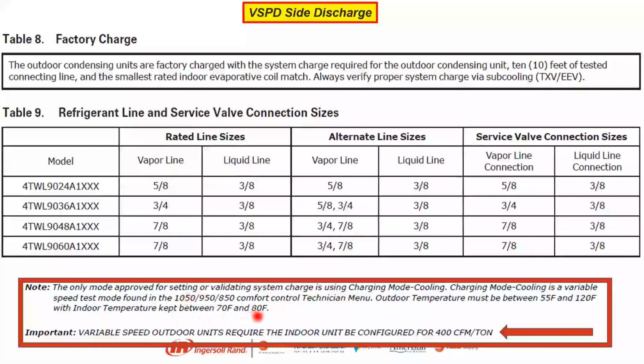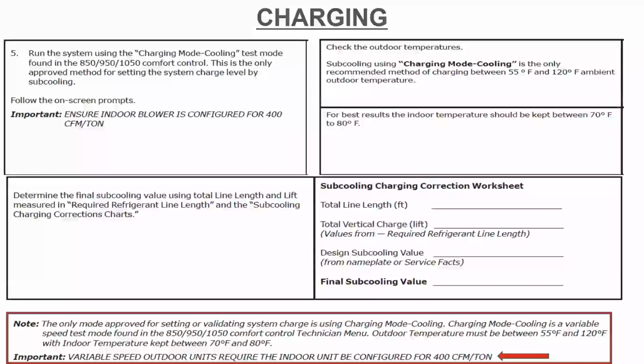Again, variable speed outdoor units require the indoor unit be configured at 400 CFM per ton when charging, which I'll touch on a little bit more. Here's our charging: total line set length, total vertical lift, design subcooling, final subcooling value. We always want that right around 10 degrees subcool.